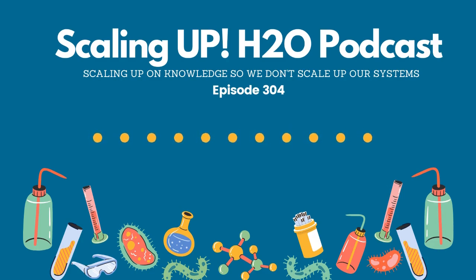I will tell you that 9 times out of 10, installation issues are what I see when corrosion coupon data does not come back proper. And I already mentioned it's not being installed in the system properly. It's not being in the right order in the system, or not handled properly either when you install them or when you take them out of the system. So if you can do all of that and then work with somebody who you can get more than just a number from that corrosion coupon from, I know that corrosion coupons are going to make you a better water treater because you're going to have more data about that system.